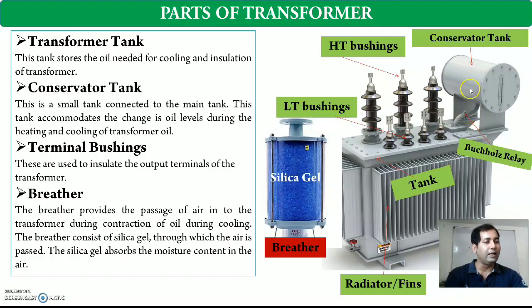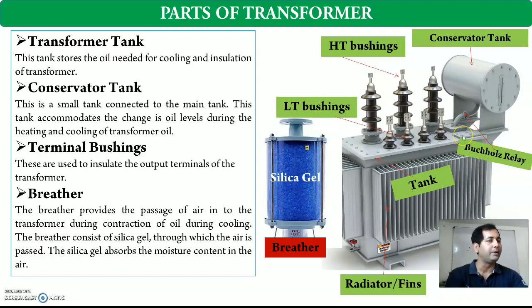The next is the Buchholz relay, a very very important part of transformer. The Buchholz relay is connected between the conservator tank and the main tank. It is a protecting device for the transformer. Whenever an air bubble is created inside the transformer oil — which can also damage the insulating property of the oil — the Buchholz relay responds. At the initial level, if there is a minor fault, it gives an alarm. If the fault is not addressed or there is a serious internal fault, it protects the transformer from being damaged by unhealthy conditions.